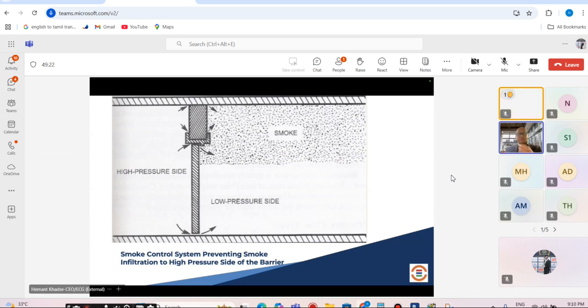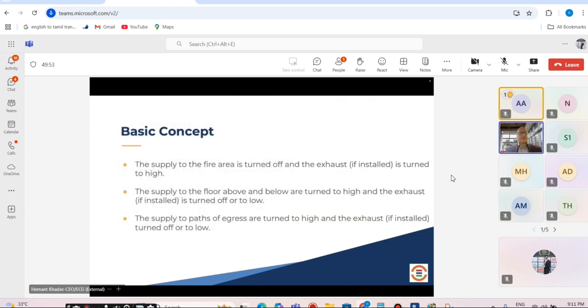But what is that Pascal? Code has always regulated minimum and maximum pressure. Minimum is 12.5 Pascal and maximum is 45 Pascal, but again, it depends on the codes and regulation. You have minimum and maximum Pascal, which is going to create that differential pressure for various zones. It could be staircase, it could be lift well, it could be lobby. And again, you have various options to do that pressurization.